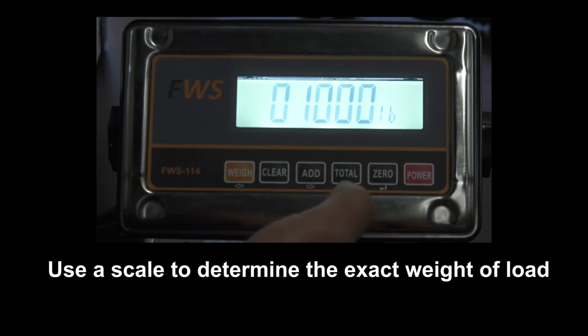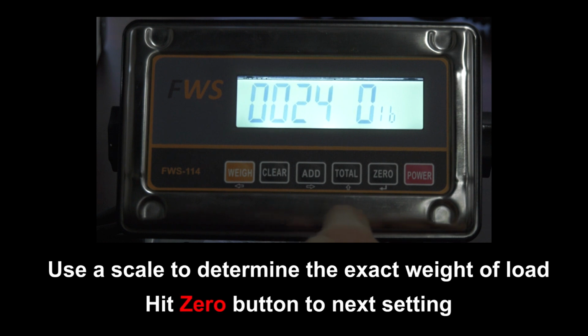The next setting is our test weight value. Using the arrows, scroll over to the digit and change the digit to the appropriate test weight. In this case, we will be changing it to 2,440 pounds. Please ensure the exact test weight value is entered in this section. Once the value is entered, press the 0 button to get to the next setting.